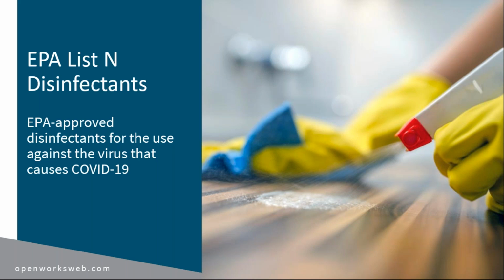So make sure you're looking at the list on the EPA site. If you have cleaners in your space, go into their janitor closet and see whether they are using the correct chemicals. Is this chemical on the list? The other important thing to check is what are called dwell times. Each disinfectant has a different dwell time: how long the surface stays wet with the disinfectant chemical. It could be anywhere from 30 seconds to 10 minutes.